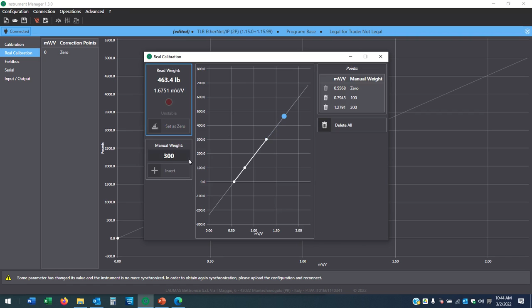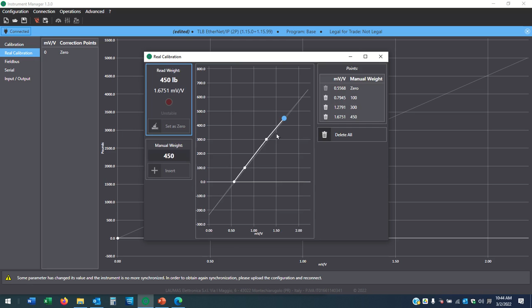And then again, I'll put this up to maybe 463. I'm going to teach this as 450 to show you how we can physically get off that curve, right? And so you can see now I've got multiple points, and when I'm done, I can physically see what I've taught this. What's nice about this is that a load cell is never used alone. Typically it's mounted to something. There are forces that are pushing, pulling, tilting that really don't apply to the application. So what you can do is mount everything up, put a known load on there, and then teach it what that load is so that you can be very, very accurate. So this is the initial line, and this is my taught line. And I can teach a bunch of points around an area to make this even more accurate. So that's how we calibrate.